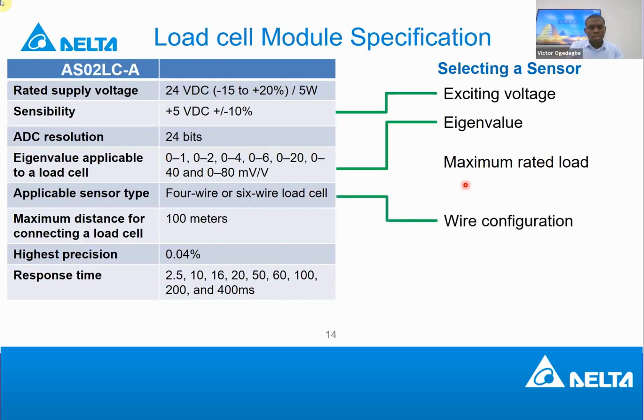Another factor when you are selecting a load cell or a load sensor is the wire configuration. For short distances, 4-wire configuration is very good. But if your machine is far, and this load sensor is far away, up to like 100 meters, then it's advisable to take a 6-wire load sensor. This 6-wire load sensor will compensate for the impedance that will be created as a result of the long distance.